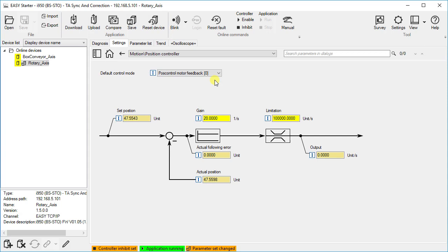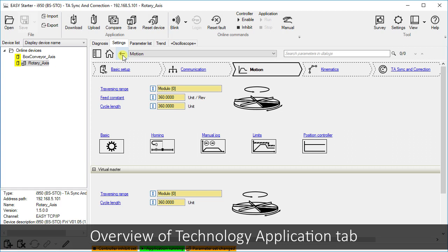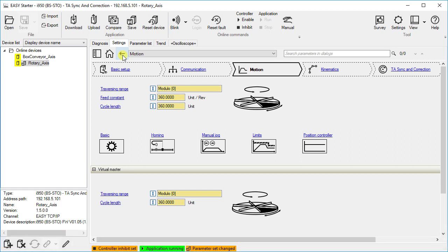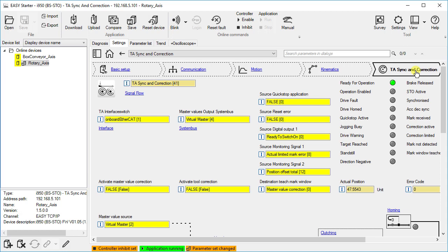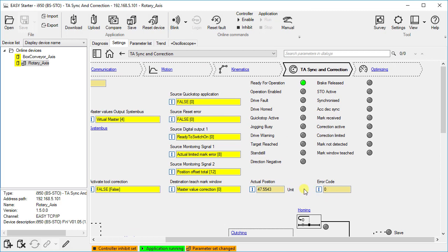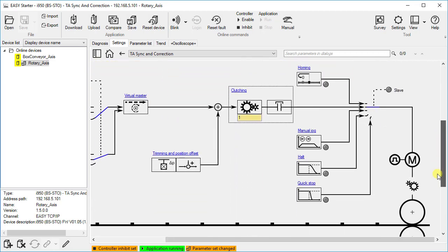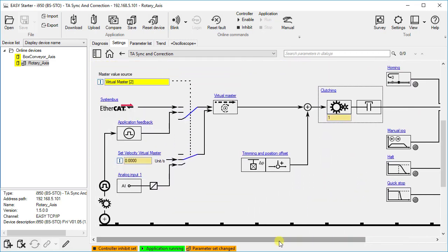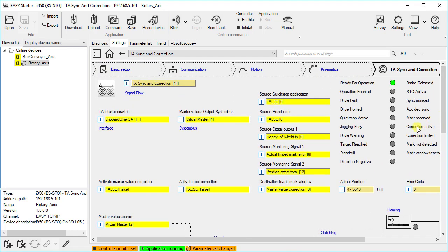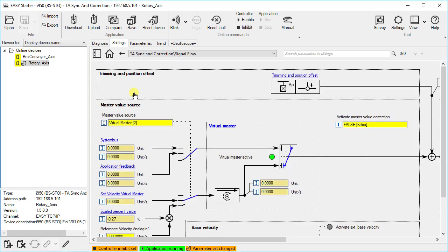This means that the most important kinematics and motion settings have been done. Next let us take an overview of the technology application, TA for short. Click on the main commissioning step of the TA — in our case the TA sync and correction. At first we are on the overview interface of the active TA. This interface view is divided roughly into three sections: the setting of essential control signals is on the left, important status signals are visualized on the right, and a simplified signal flow is visible below. Click on the signal flow to find more details like the source values and connected paths of signals to the drive.